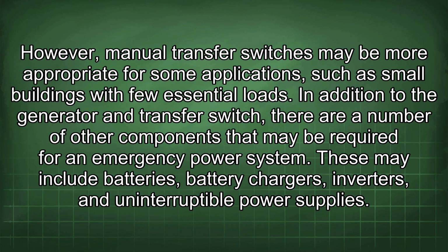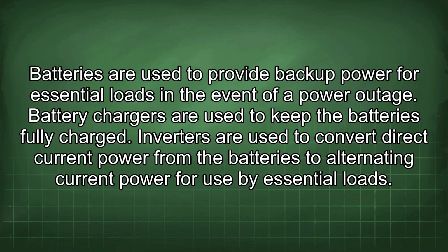In addition to the generator and transfer switch, there are a number of other components that may be required for an emergency power system. These may include batteries, battery chargers, inverters, and uninterruptible power supplies. Batteries are used to provide backup power for essential loads in the event of a power outage. Battery chargers are used to keep the batteries fully charged. Inverters are used to convert direct current power from the batteries to alternating current power for use by essential loads.